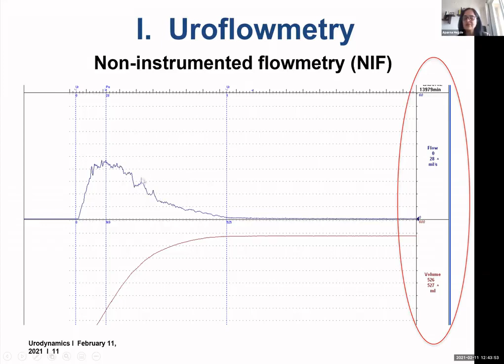You see, there is an upswing and then there's a downswing that is slower. And this up and down that you see here is artifact. The woman is moved, so you have an artifact here. But generally, this is a very good flow. This is what you normally get, a very good one. And when you get a graph and measurements, what do you see? You get the maximum flow rate, the average flow rate, the voided volume, the time to maximum flow, the flow time, and the voiding time.